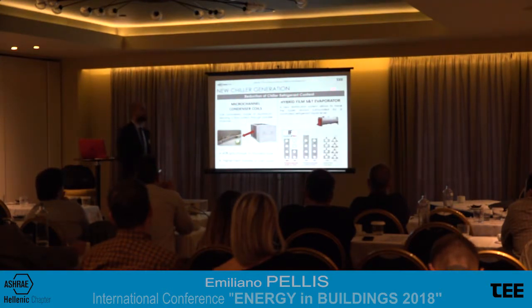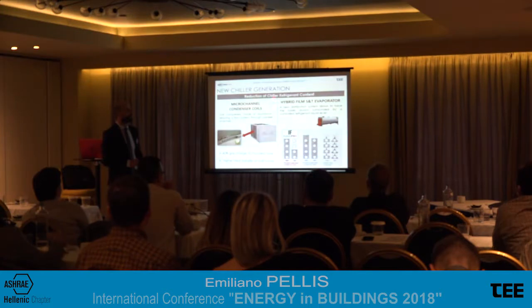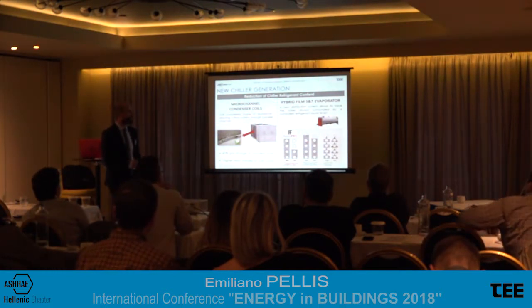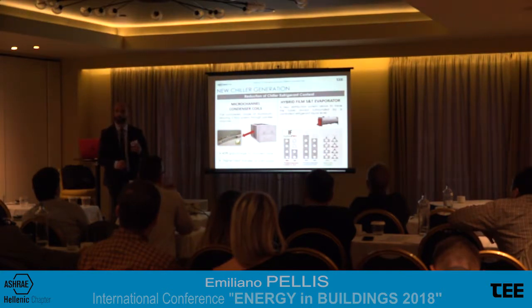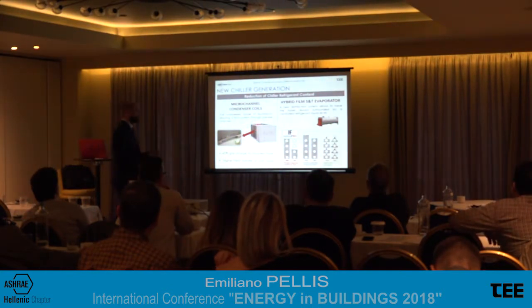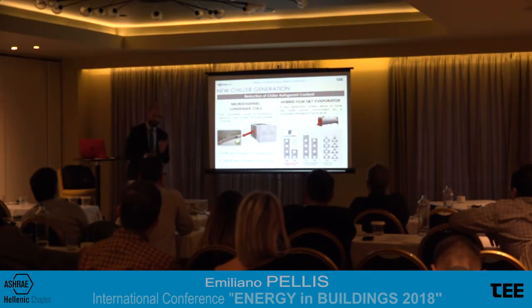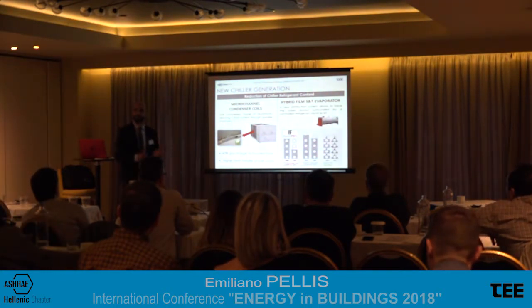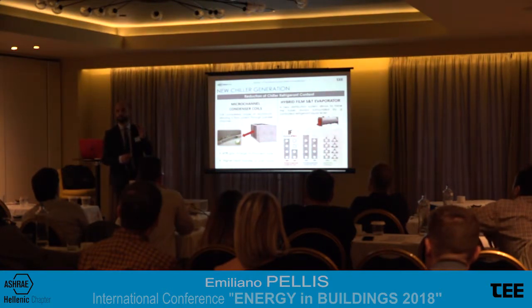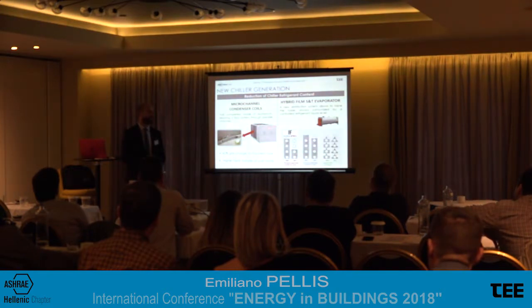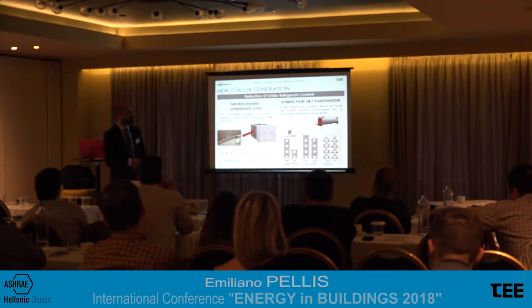So, reduction of chiller refrigerant content. This is possible by using some technologies. I have reported here a couple of examples. The microchannel condenser coils instead of the standard copper aluminum coils. It is a system made completely of aluminum, and basically through the system of parallel channels, we not only achieve an improvement in terms of efficiency thanks to the larger surface for the heat exchange, but we also reduce by 35–40% the refrigerant content of the unit. So this is very important, and this is normally an option on the chillers provided by all the manufacturers. Sorry, this comment is related to the part on the right.